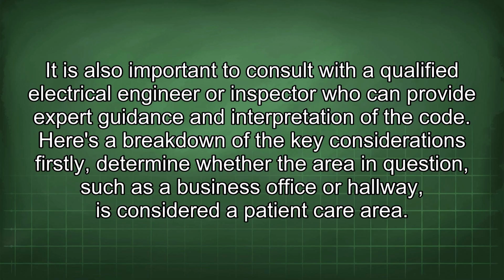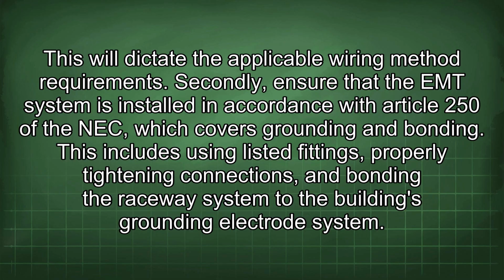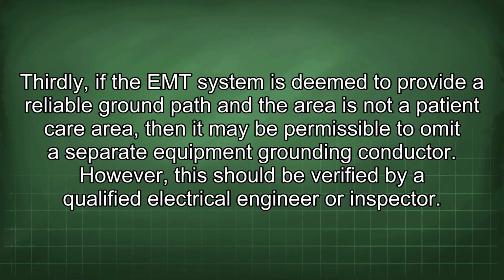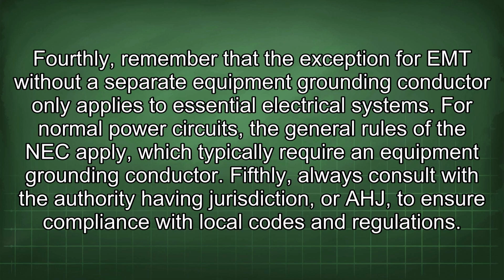Firstly, determine whether the area in question, such as a business office or hallway, is considered a patient care area. This will dictate the applicable wiring method requirements. Secondly, ensure that the EMT system is installed in accordance with Article 250 of the NEC, which covers grounding and bonding. This includes using listed fittings, properly tightening connections, and bonding the raceway system to the building's grounding electrode system. Thirdly, if the EMT system is deemed to provide a reliable ground path and the area is not a patient care area, then it may be permissible to omit a separate equipment grounding conductor. However, this should be verified by a qualified electrical engineer or inspector. Fourthly, remember that the exception for EMT without a separate equipment grounding conductor only applies to essential electrical systems. For normal power circuits, the general rules of the NEC apply, which typically require an equipment grounding conductor.